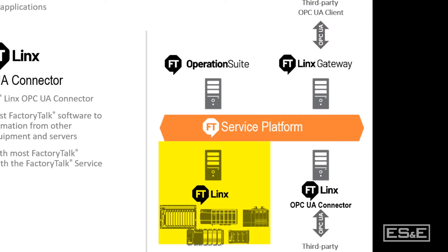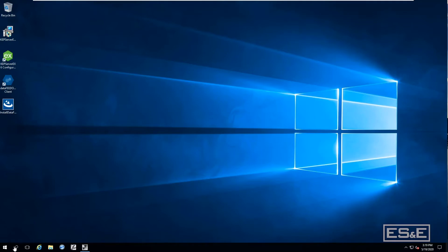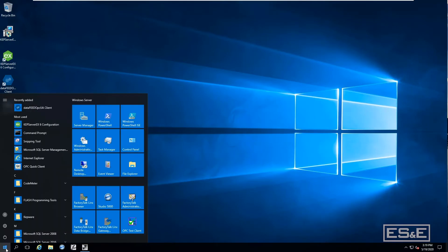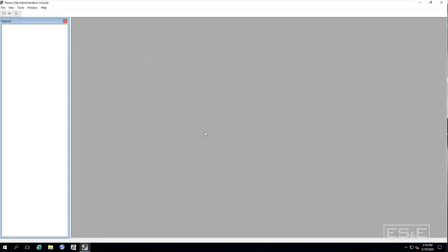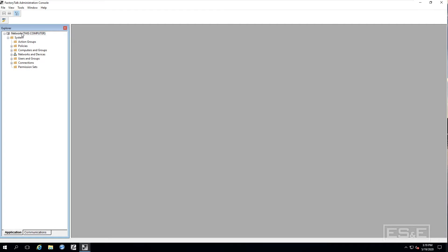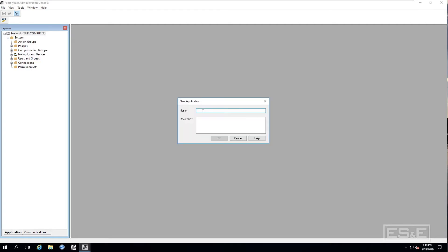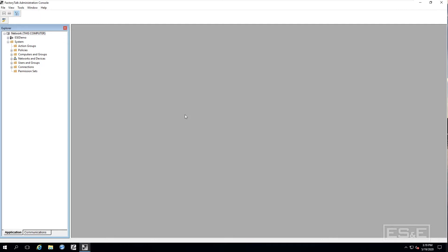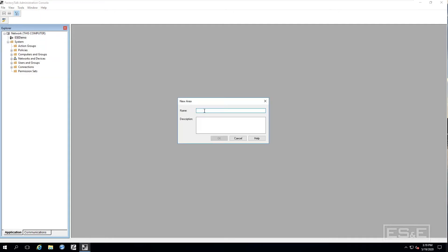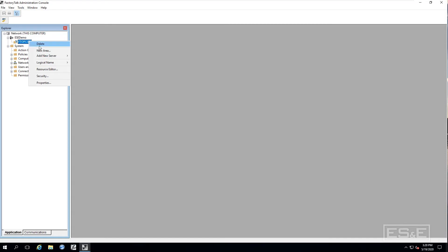To be able to make all this work, we must first set up FactoryTalk Linx to communicate with the controllers. So the first thing we have to do is open up Factory Talk Administrative Console. Then we will create a new application. There we are going to define a new area. Now in that area we are going to define a FactoryTalk Linx data server.